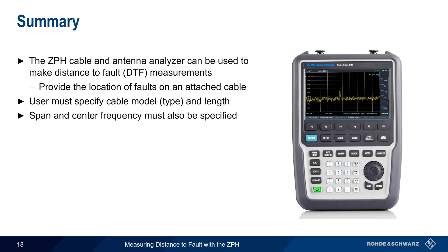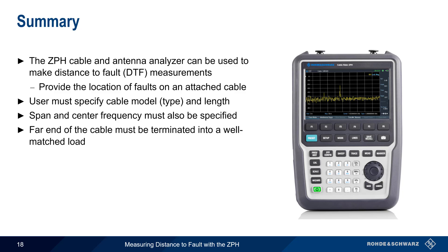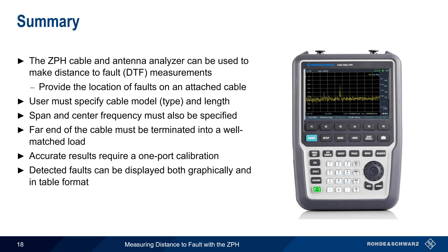When making distance-to-fault measurements, it's important to remember that the far end of the cable must be terminated into a well-matched load or resonant antenna. Accurate DTF measurements also require a valid one-port calibration. Measurement results are usually displayed in the form of a graph showing return loss as a function of distance, although faults can also be shown in tabular format. Finally, markers can be used on the trace results to obtain more precise numeric values.